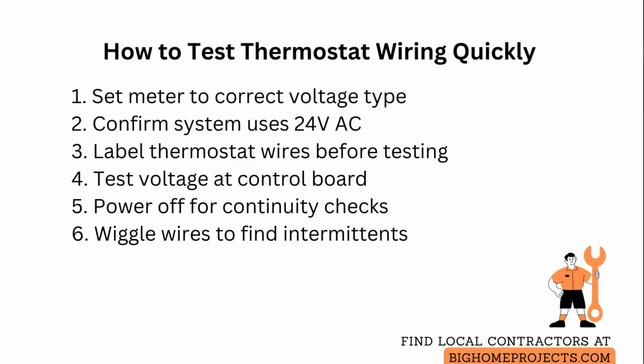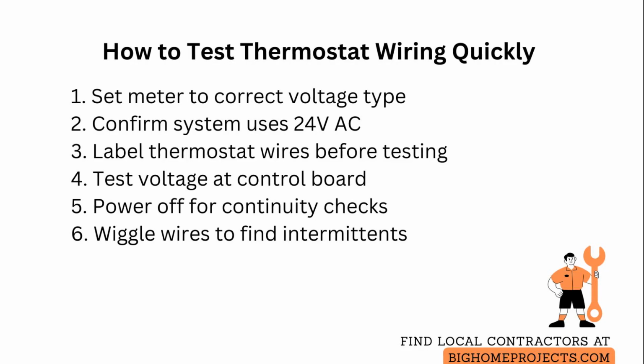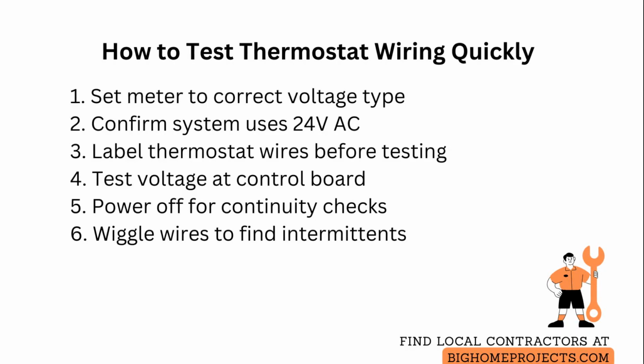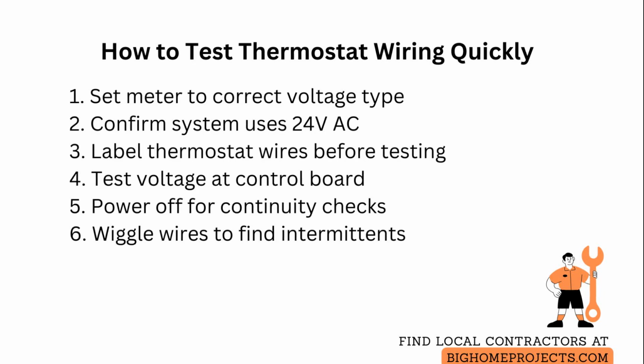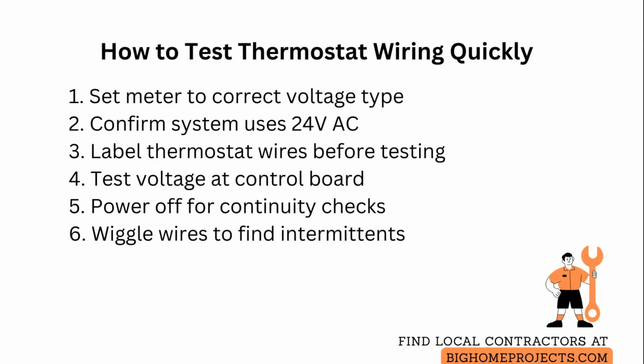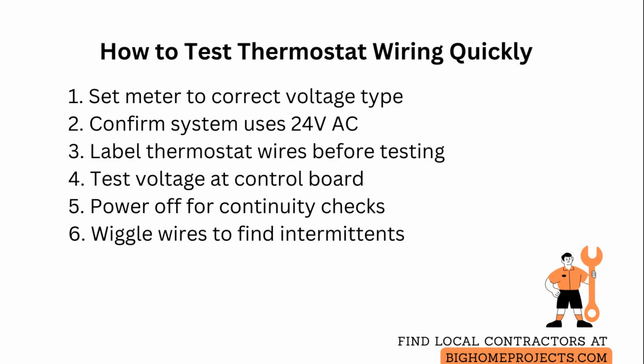For continuity tests with power off, set the meter to the continuity or resistance range and check each wire end to end. An open circuit indicates a broken conductor, while very low resistance indicates good continuity. Document readings and compare them to expected values from the equipment manual, and if readings fluctuate or are intermittent, gently wiggle wires and retest to locate intermittent shorts caused by frayed conductors or poor terminations.